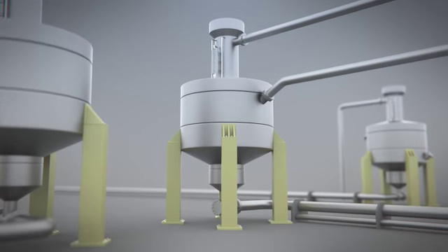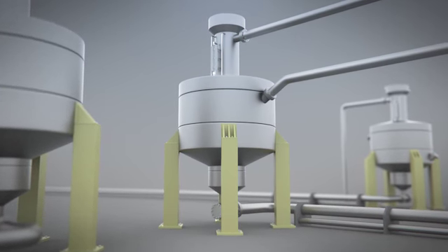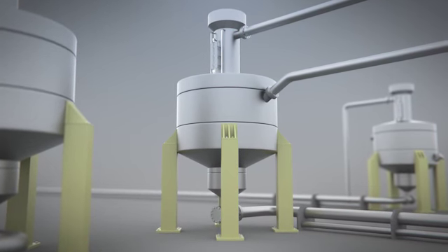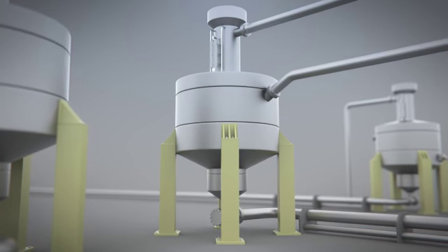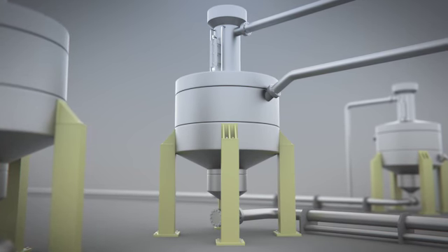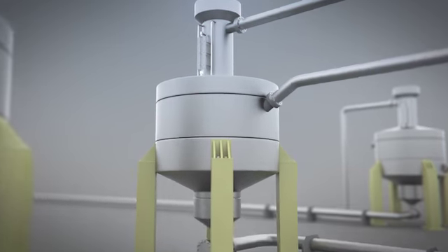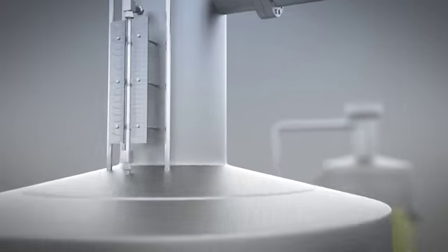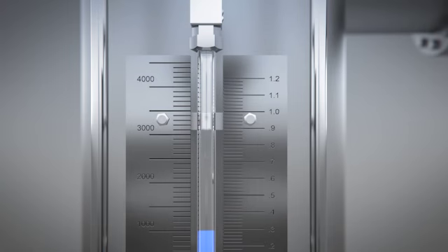In practice, besides the gravimetric measurement method, a volumetric calibration method is also applied. Instead of a weighing scale, the volumetric method uses a measuring container. The quantity of water collected in it is measured by a precision volume gauge.